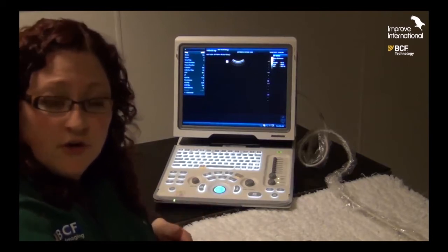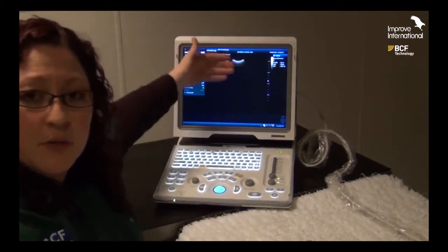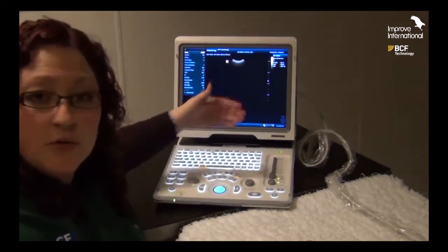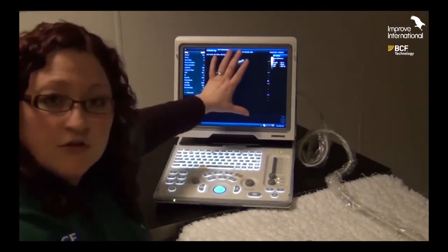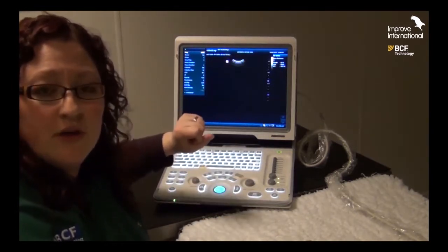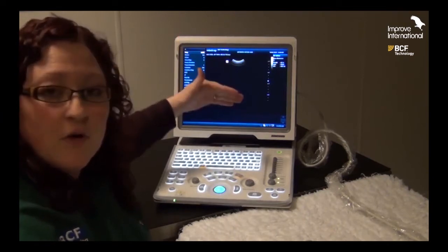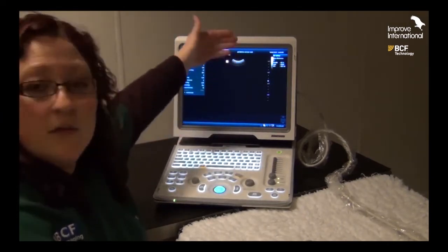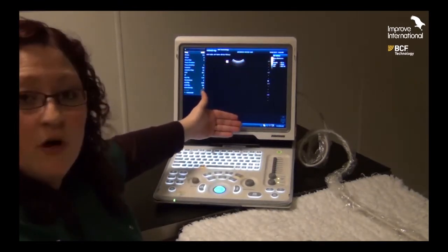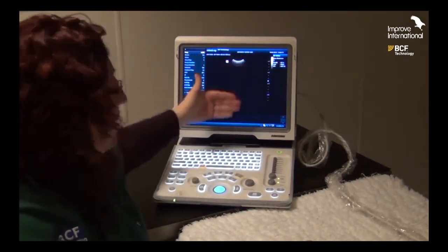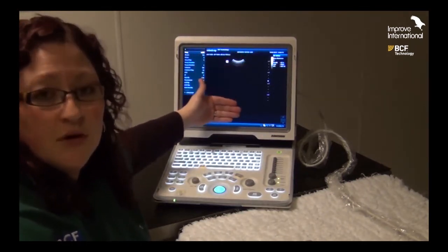The converse is also true, in that if we're expecting the wave to travel deeper down because we have an increased depth setting on our ultrasound image, we'll therefore need to decrease the frequency setting so that we improve the penetration and we have a nice image all the way through, from the top or the superficial structures down, lower down, or deeper.